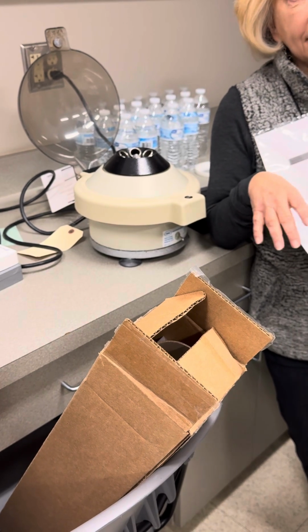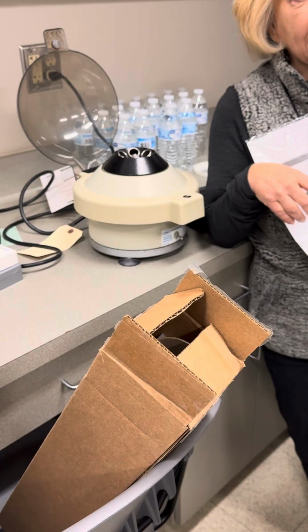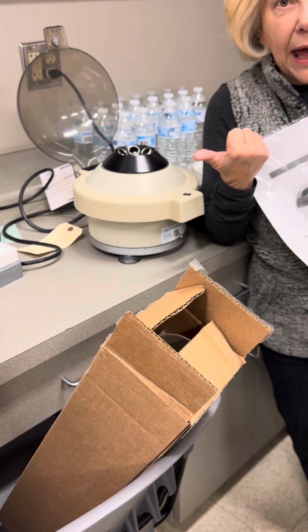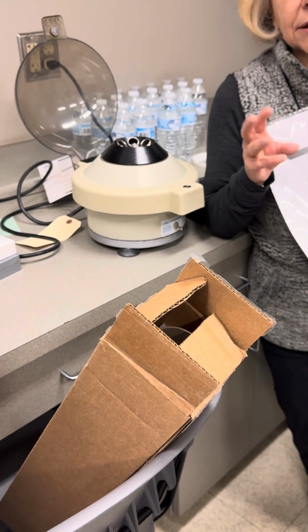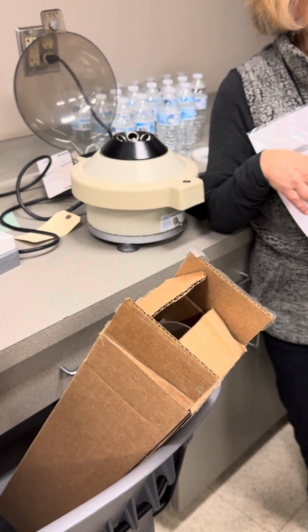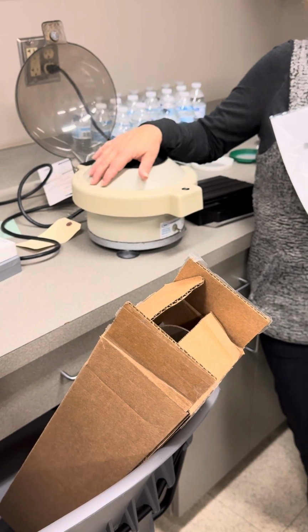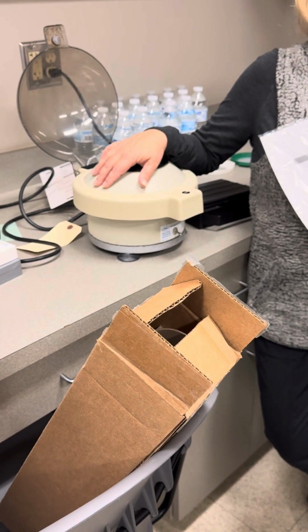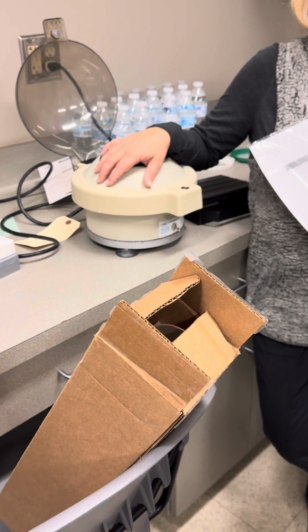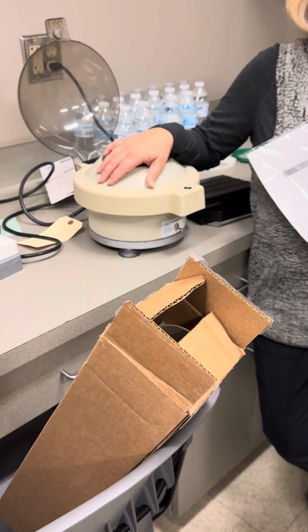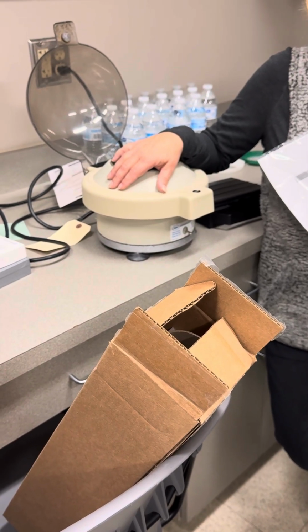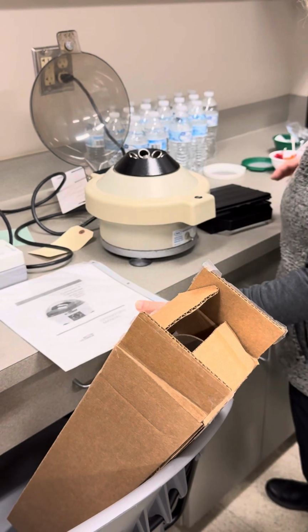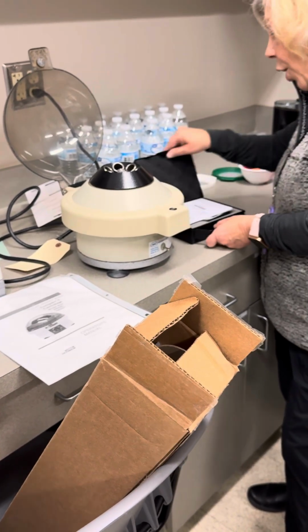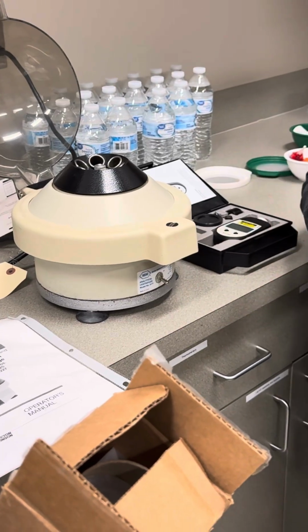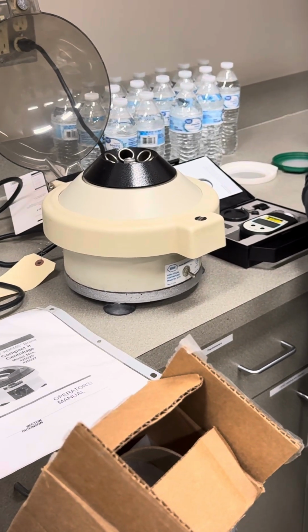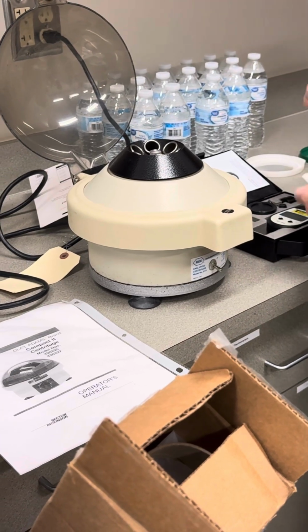But a lot of the times when we go into the hospitals again, they talk about the blood's always hemolyzed, or, you know, it's got a clot in the machine, and we're trying to explain to them that their centrifuges are no longer working at the correct RPM, and that they will need to add, if we don't have one with us, we tell them instead of 15 minutes, you're going to need to do 20 to 30 minutes for good separation, the time. So that's what we'll see. But we will check it for them while we're there. We hope that their biomed department would do that for them, but they don't always. You know, they don't know how.